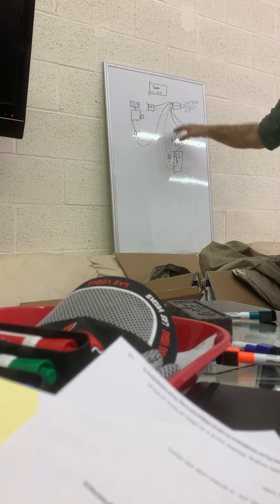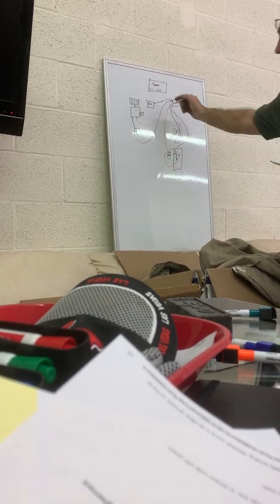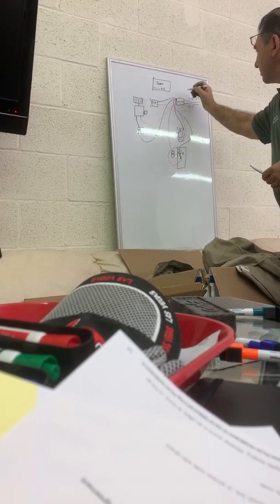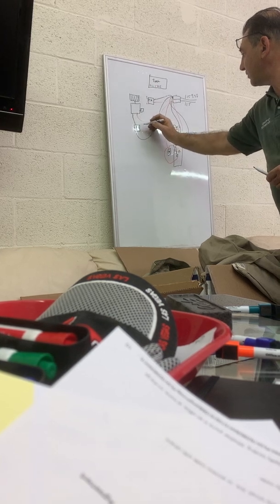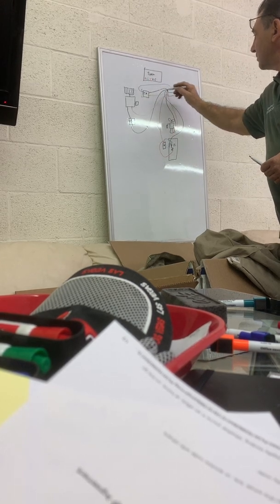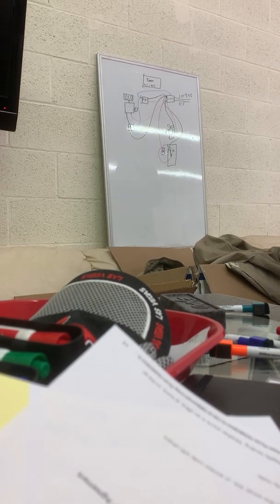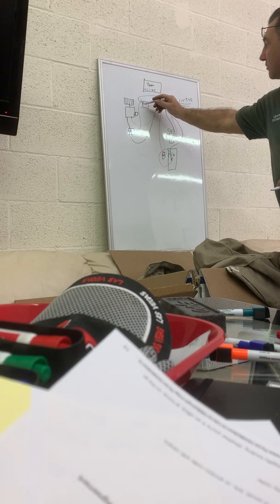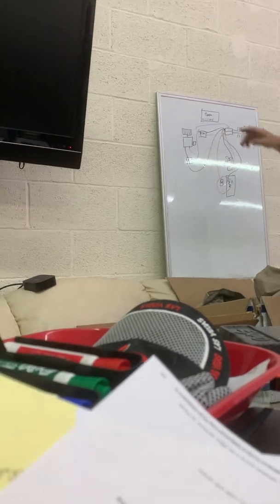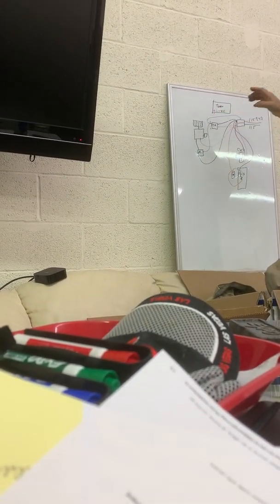Now we're going to connect common to all the components we have. We have a contactor and a relay, so one wire goes to the contactor, one to the relay. Now R goes to the thermostat, and from the thermostat, R will distribute to the other components.